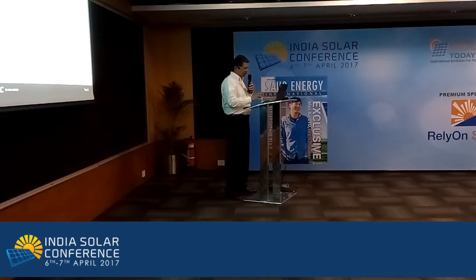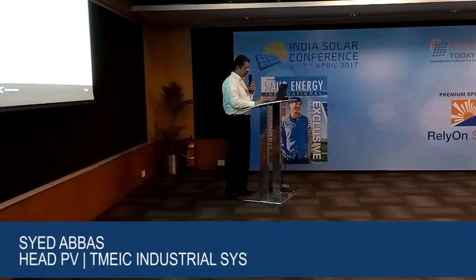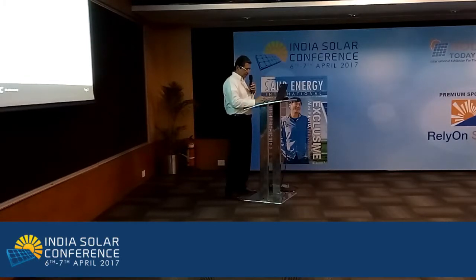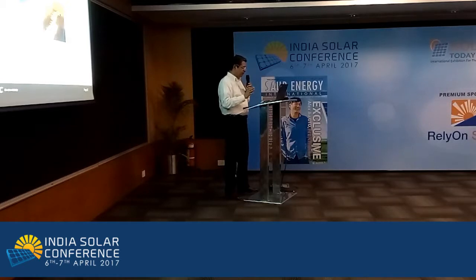The most important thing we follow is that for each and every system we do a thermal analysis, validate the fluid dynamics, and optimize for the specific local footprint of the site, looking at the impact of the inverter in that area, whether it's Rajasthan, Gujarat, or the south in India. We then validate that technology, run the heat run test and so on, and deploy it to the field, because we want a fit it, shut it, forget it approach. It's not possible to send people to monitor, say, 5 gigawatts of installed base and ensure uptime.